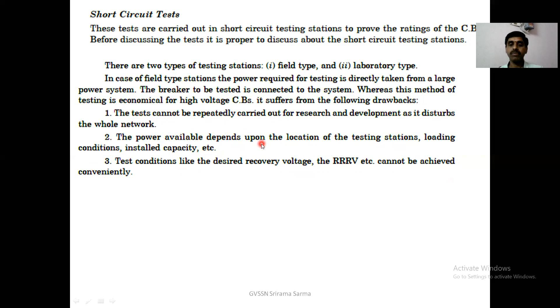This method of testing is economical for high voltage circuit breakers, but it suffers from the following drawbacks. What are the drawbacks? The test cannot be repeatedly carried out for research and development, as it disturbs the whole network, because we are directly taking the supply from the large power system. The power available depends upon the location of the testing station, loading conditions, installed capacity, etc. Test conditions like the desired recovery voltage, TRV, etc. cannot be achieved conveniently in field type testing.